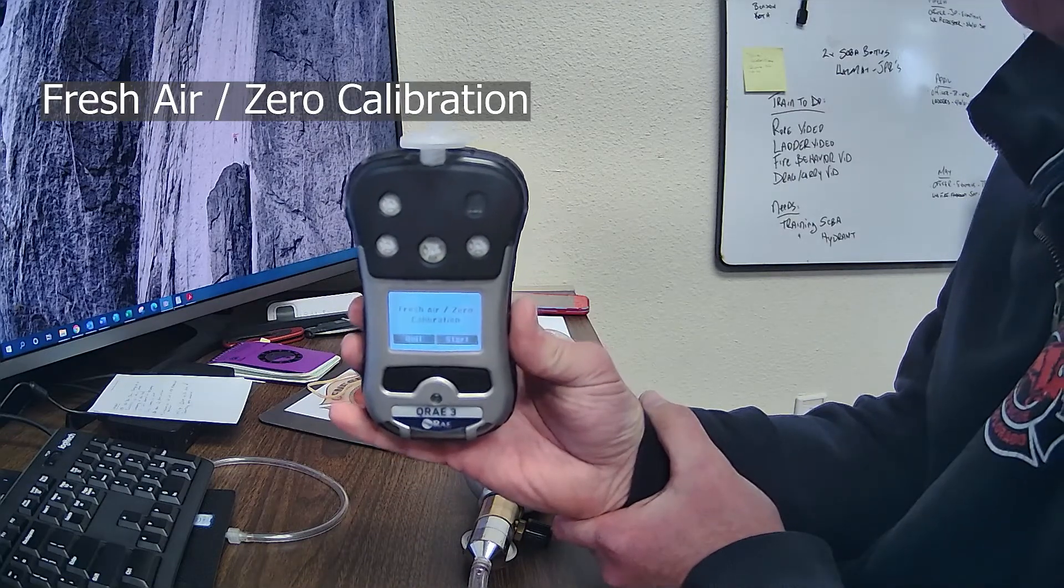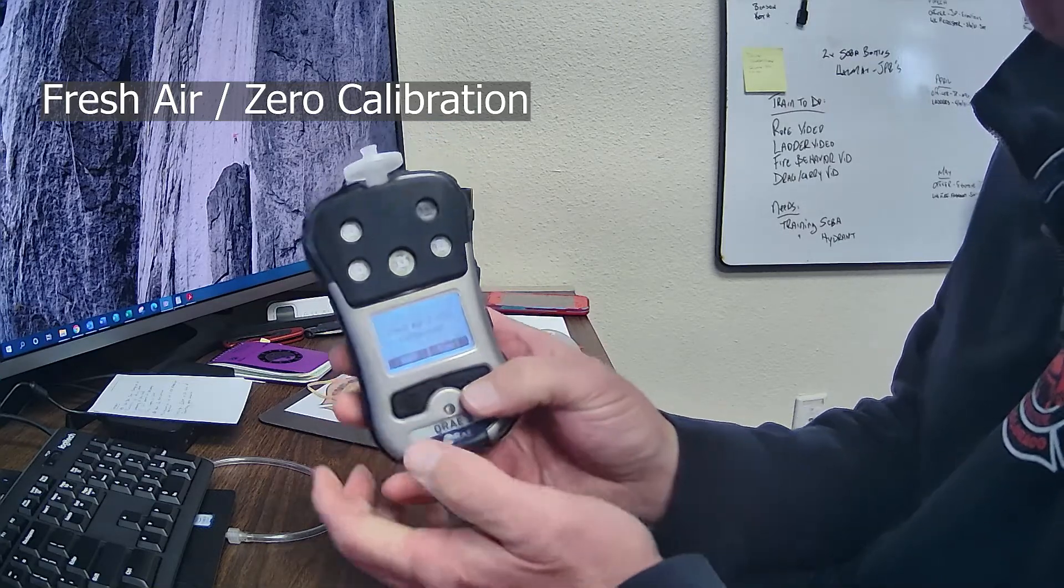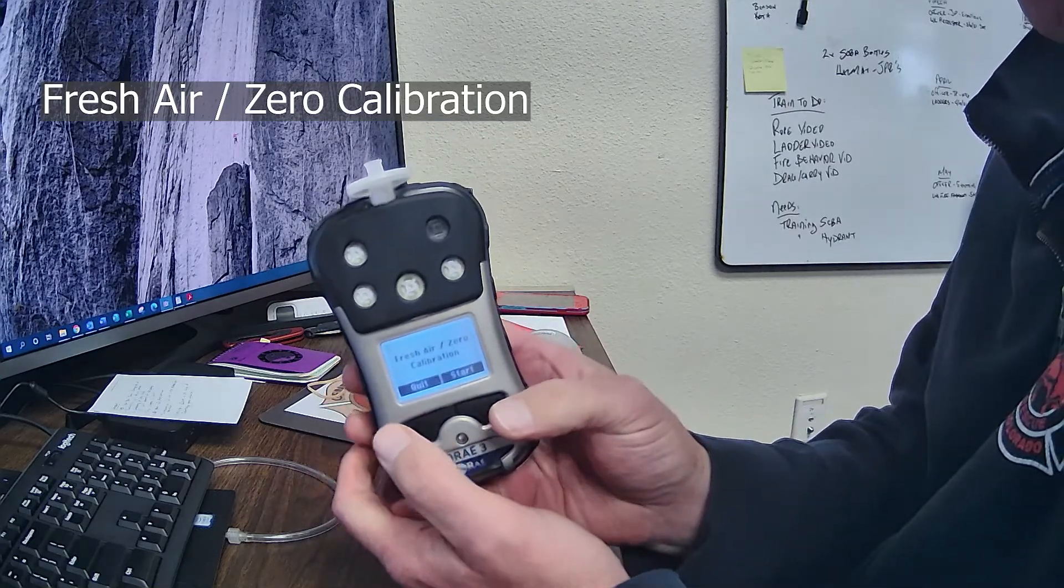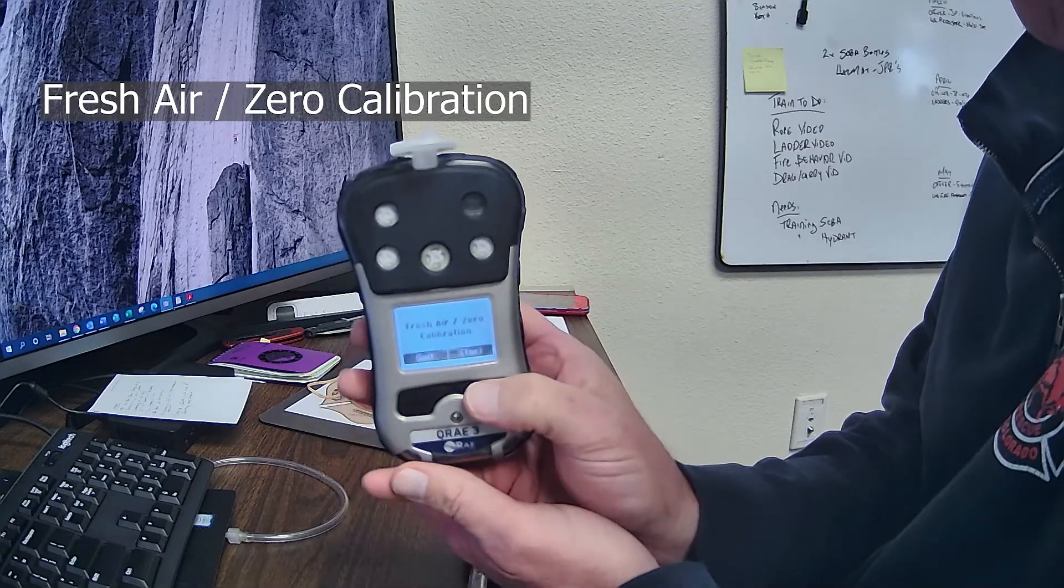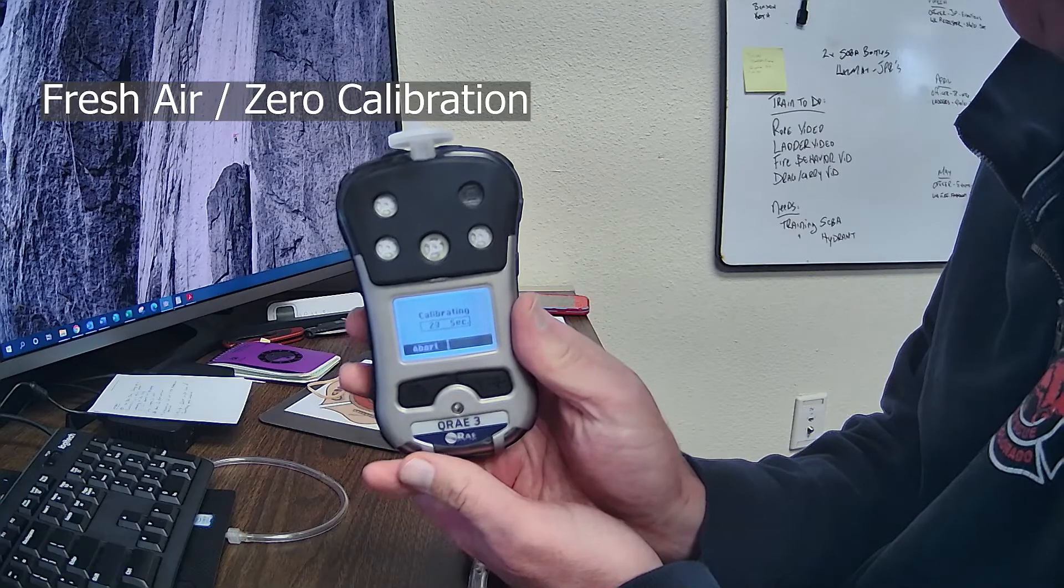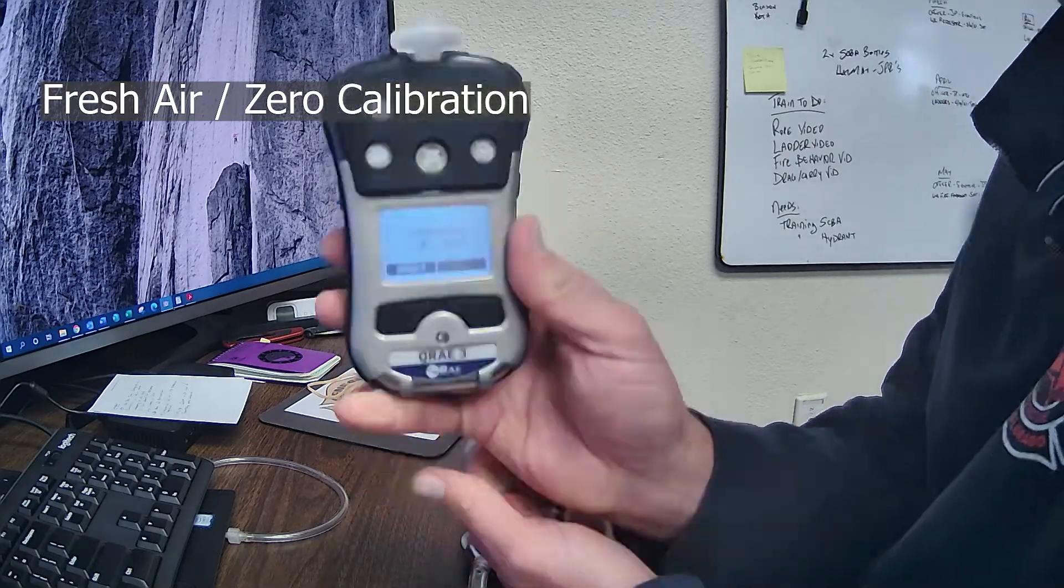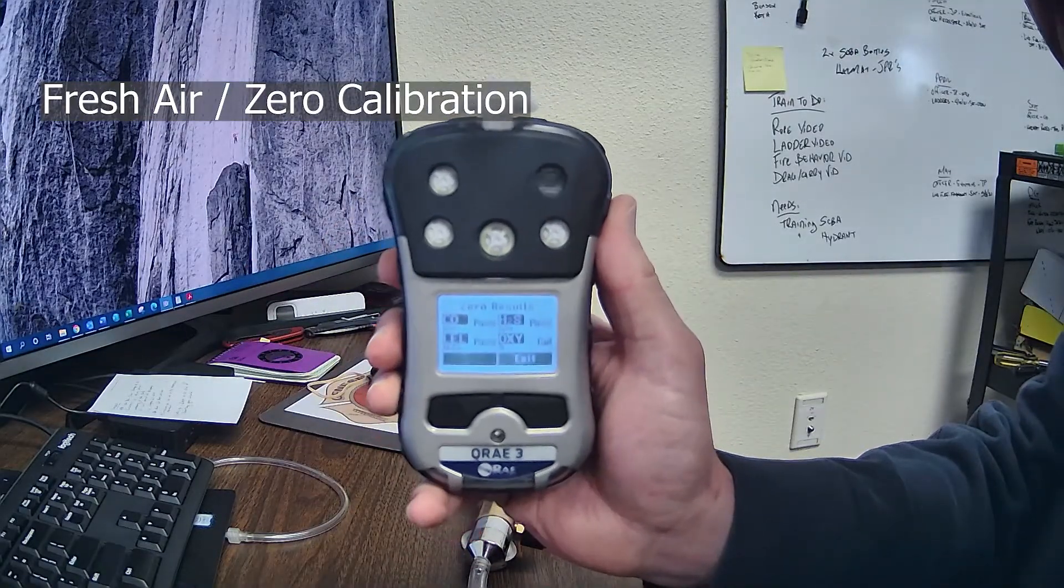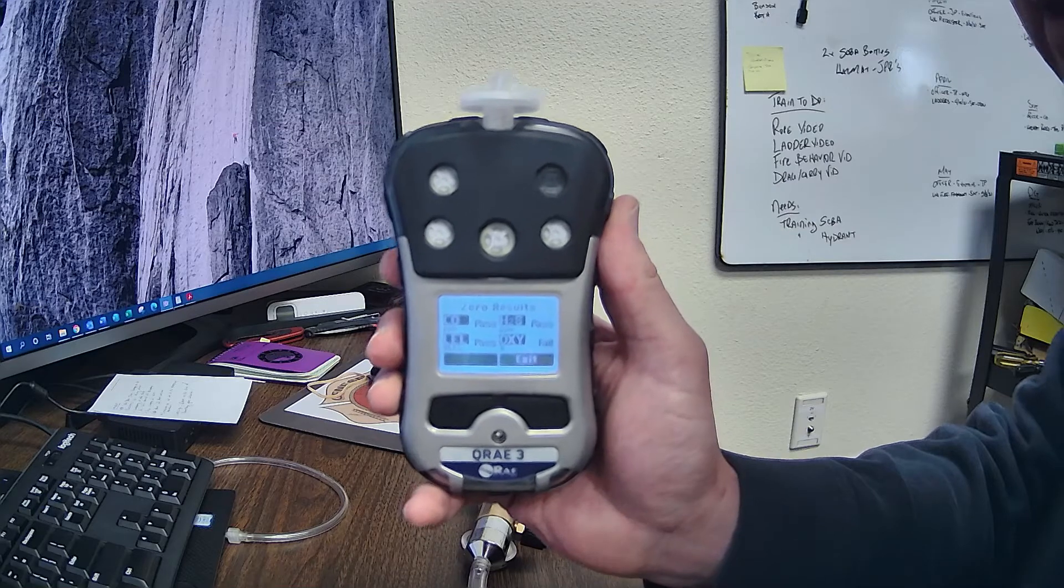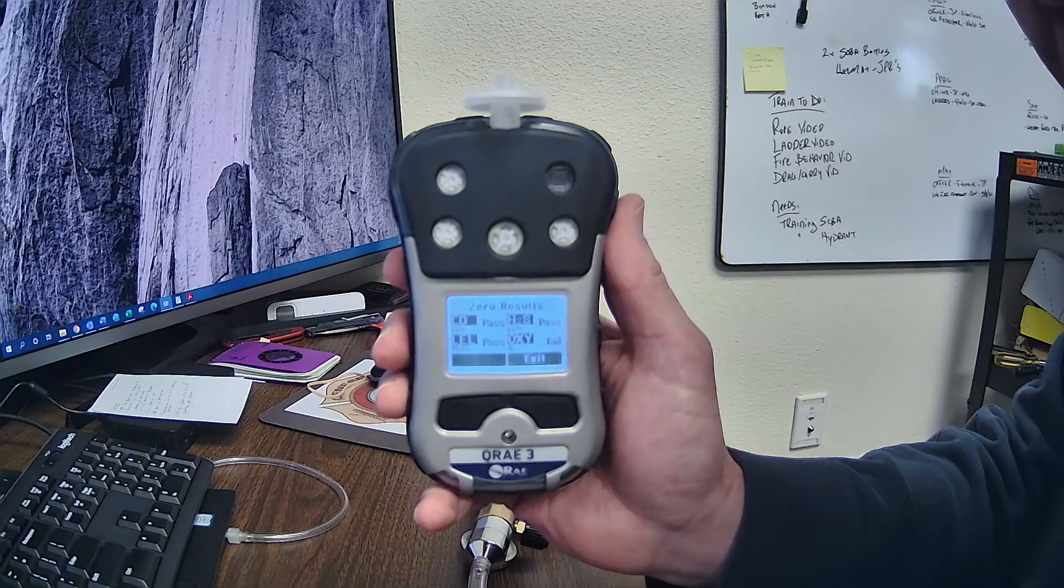So fresh air is zero calibration. You can either quit, they're a little bit different than the other one. You can quit, or you can start. So if you want to start the fresh air zero calibration, go ahead and do that. Takes about 27 seconds. Okay, calibration readings show pass, but the oxygen sensor failed. Ooh, that's not good.